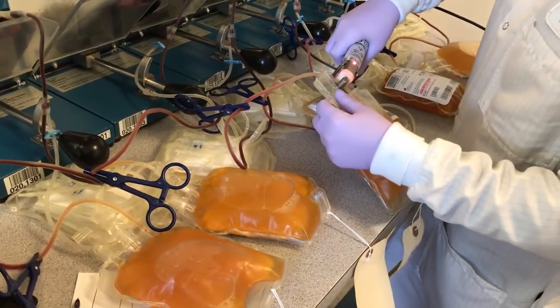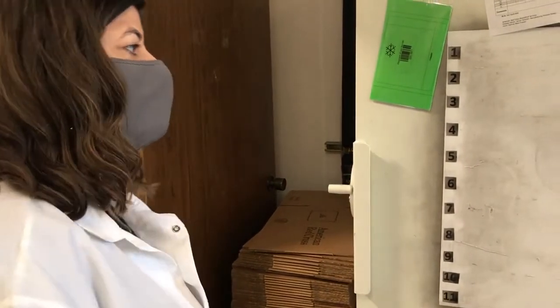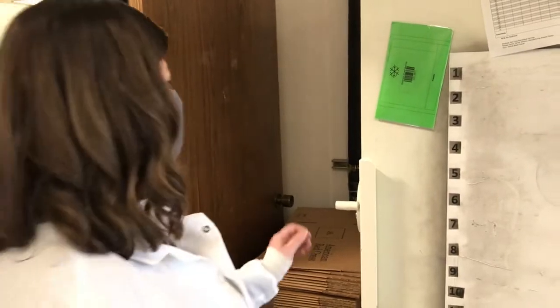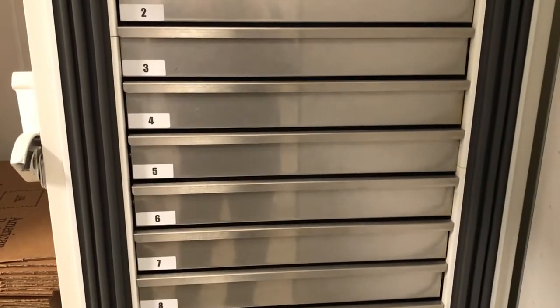The plasma is then frozen in blast freezers. These are our two blast freezers — both over 15 years old. We are asking to replace one this fiscal year and one the following fiscal year. New blast freezers are much more economical — they're self-contained and have less downtime and less repair. The blast freezer is designed to freeze plasma solid within a two-hour timeframe, has a large fan in it, and runs at minus 50 degrees.